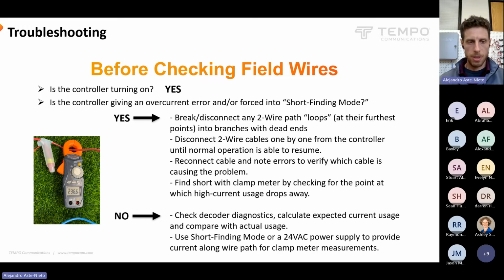And if it's not an overcurrent problem, we can still use the clamp meter to our advantage to find where that problem is. We can ideally put the controller into short finding mode or wire test mode to give us that source of current, rather than the funky waveform that it might be operating on when it's idling. Or again, we can provide our own power supply to supply a current for our clamp meter.